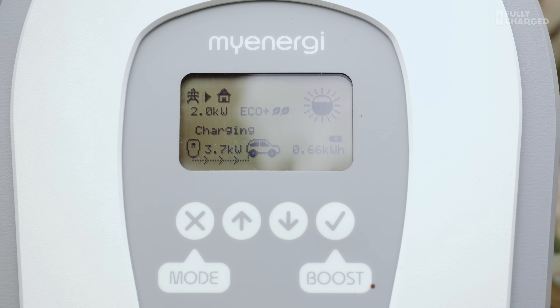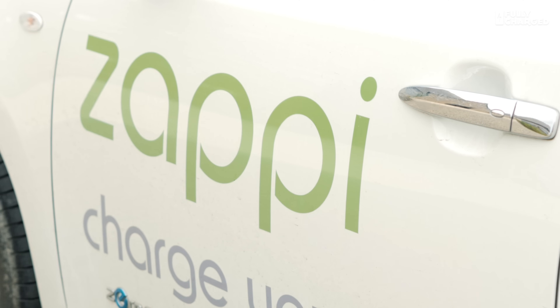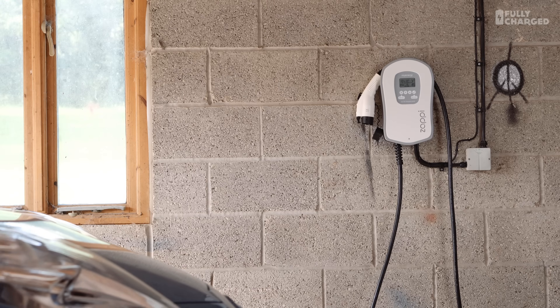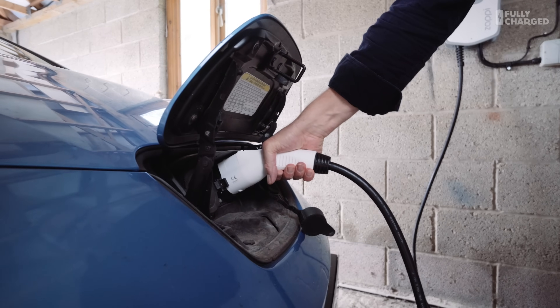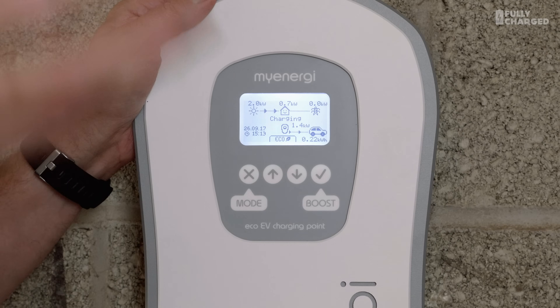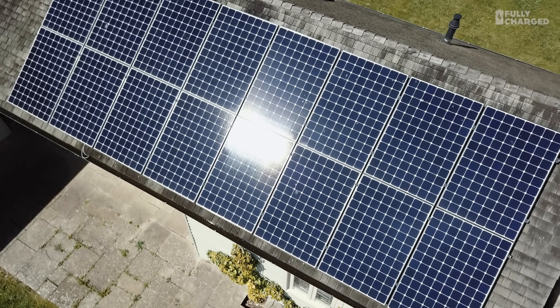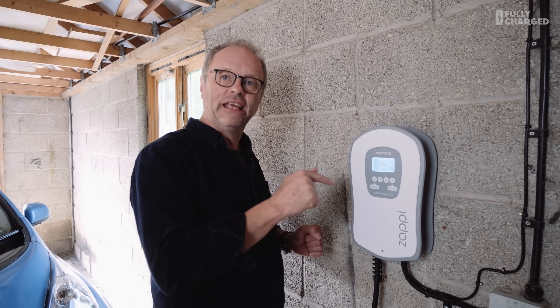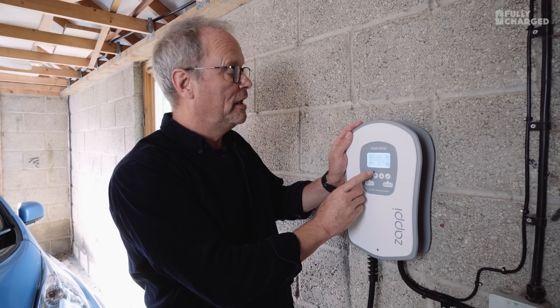This is my Zappi charger — it's only been fitted a couple of weeks ago. The basics are simple: you've got solar panels on your roof and an electric car. All the energy the solar panels produce goes into your house first. Any excess would normally go out to the grid. What this system does is read what you're sending to the grid and puts it into the car instead. At the moment the solar panels are producing 1.9 kilowatts, the house is using 0.6, so the remaining 1.4 kilowatts is going into the car.